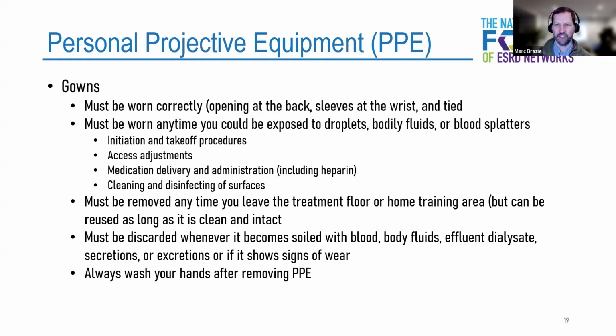Anytime the access is being adjusted - so the patient's on the machine and you're getting a high venous access pressure, and the PCT comes over to manipulate the needle to reposition it slightly - they need to be wearing full PPE because they're manipulating the access. Anytime a nurse is administering medication, they also need to be wearing full PPE.